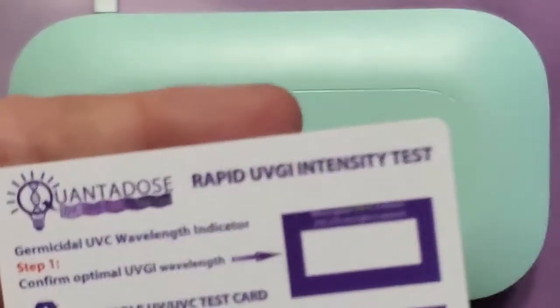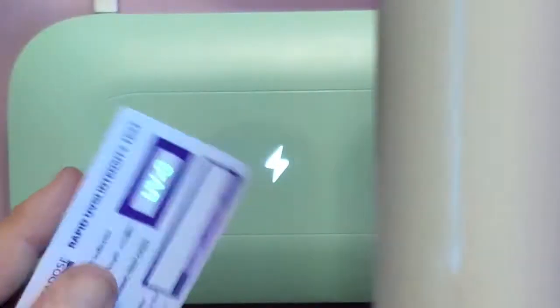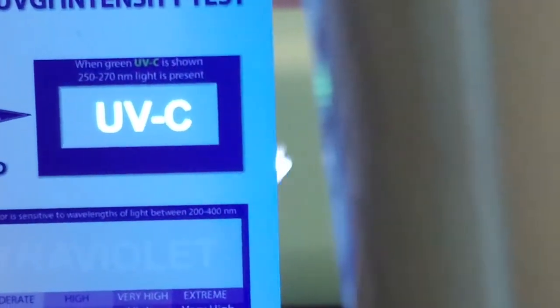Here we go — this is the Quantadose test card, and it has a specially formulated ink chemistry that allows it to be sensitive only to germicidal wavelengths. As you can see, the word 'UVC' is glowing brightly when we put it underneath the UVC light, so it's detecting germicidal wavelengths.